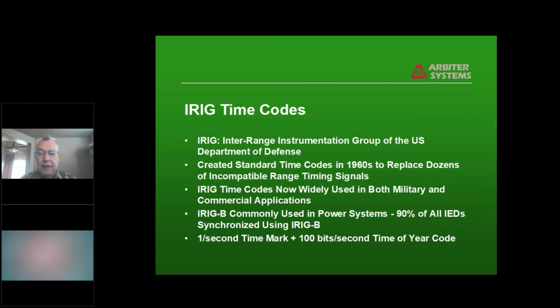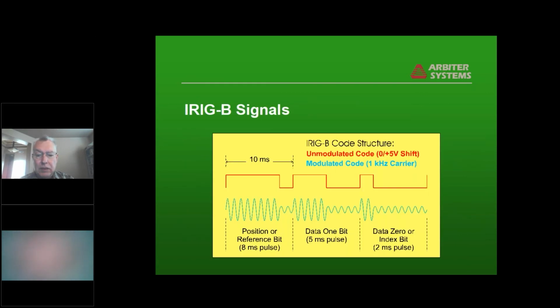And once they became standardized, they became used basically universally in the military, including NATO and other applications, as well as in the power industry. And IRIG-B is still commonly used in power systems. At the time I wrote this, 90% of all IEDs were still synchronized using IRIG-B. At this point, there's a larger number that are using SNTP, and some people are using PTP now, but IRIG-B is still kind of the backup timing method if we want simple, reliable time in an IED. And it provides basically a 1 per second time mark like 1 PPS, plus it gives you 100 bits a second of data, which has time of year and some other information on it.